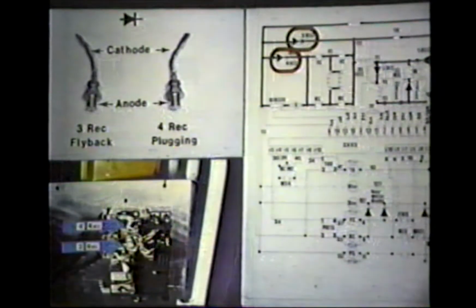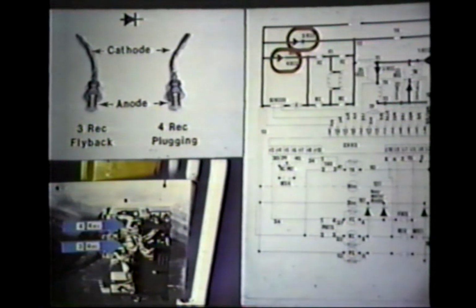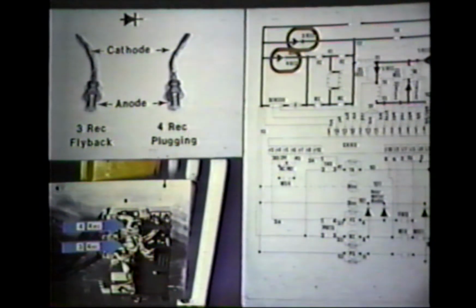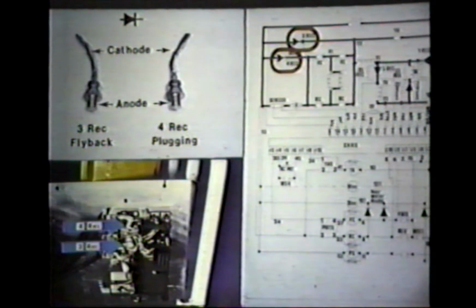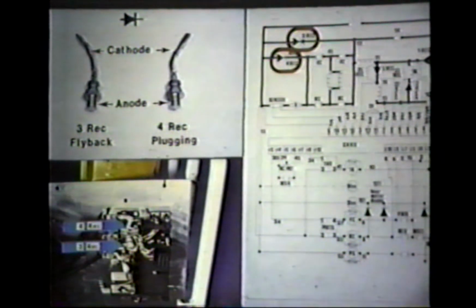The flyback and plugging diodes are mounted in the center of the panel. Although the 3 and 4 recs look similar, they have different amperage ratings and therefore are not interchangeable. Also, the polarity of these diodes is opposite to the 3 or 4 recs used on the Model 100-500 panels. Interchanging diodes between the two controls will result in a dead short in the control.